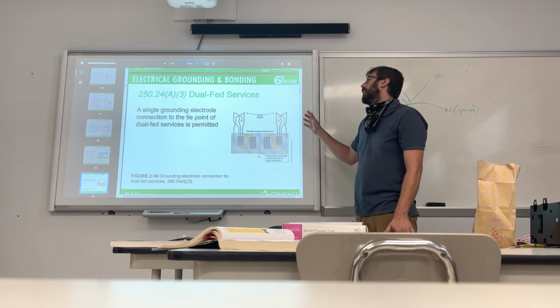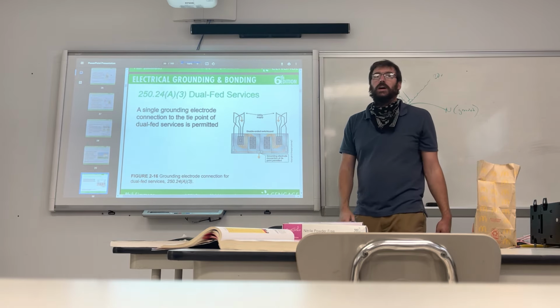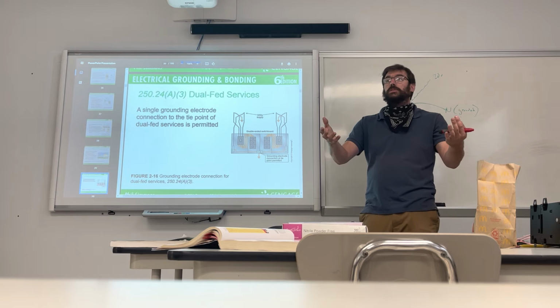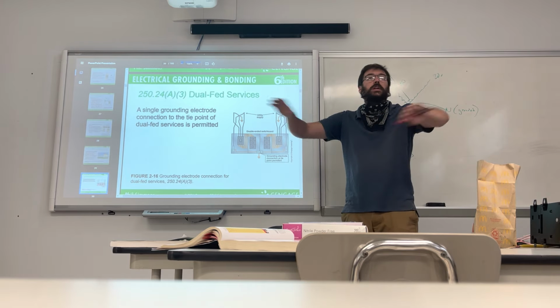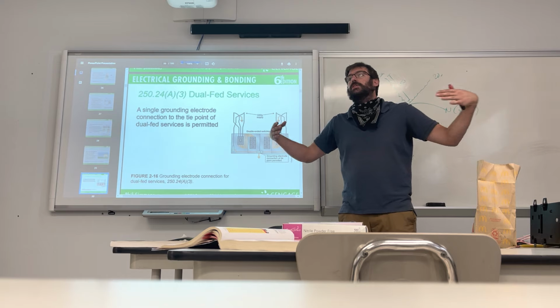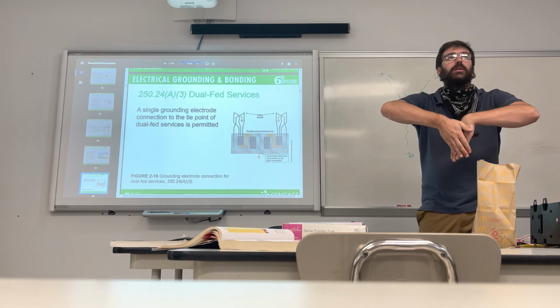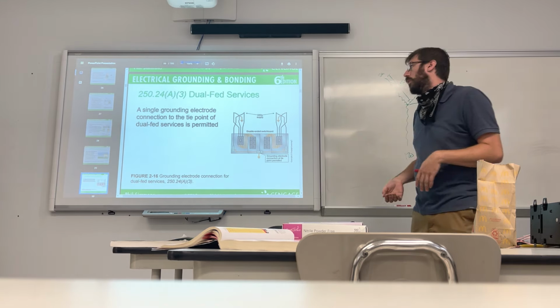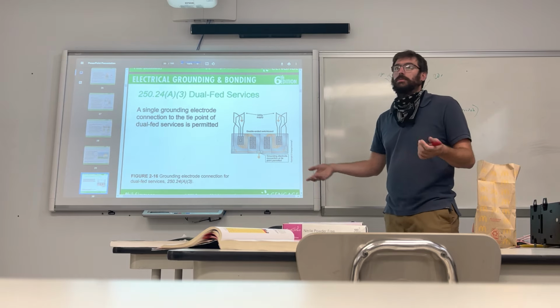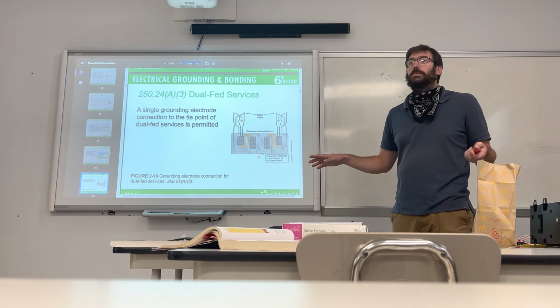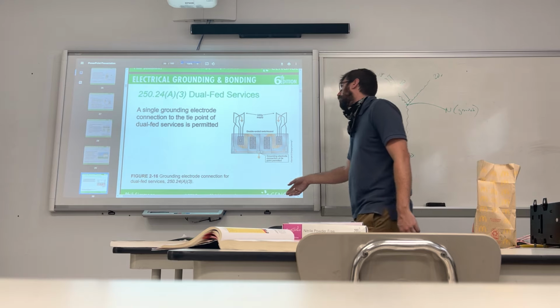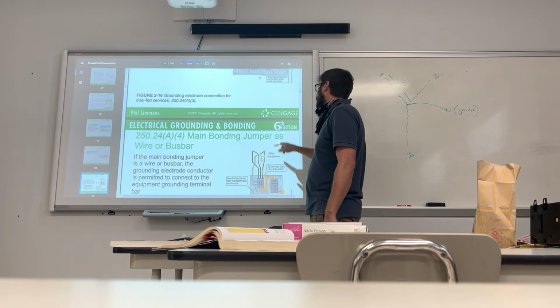So just know that that is permitted, but it's not very often. Normally when you have two services coming to the same building, they are on opposite ends of the world. You know what I mean? So there'd be no real need to combine that ground for that one purpose. There'd be a lot of wire wasted. So normally they would have two separate grounds, just as if it was two separate buildings. But just know this is permitted, but it doesn't happen very often.